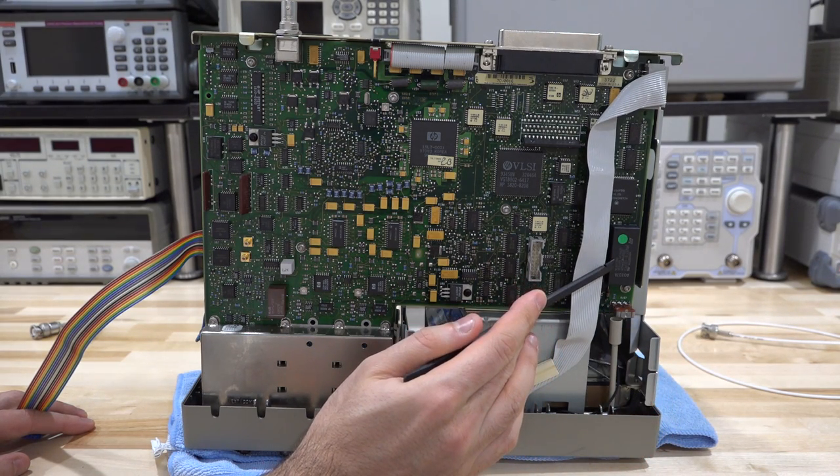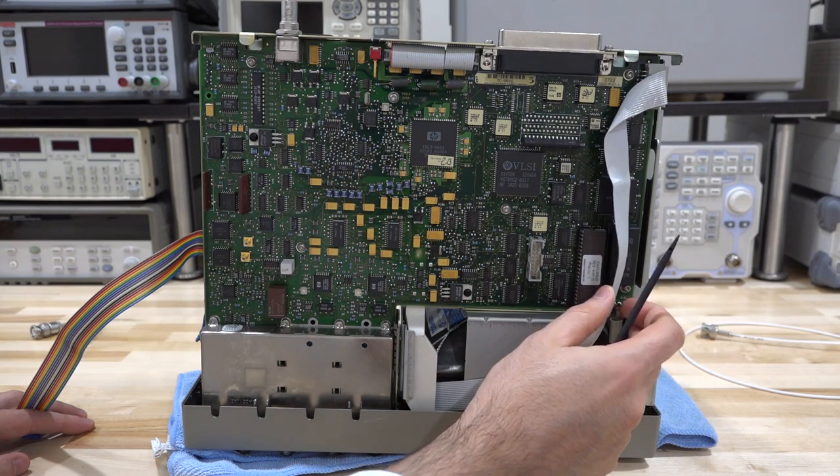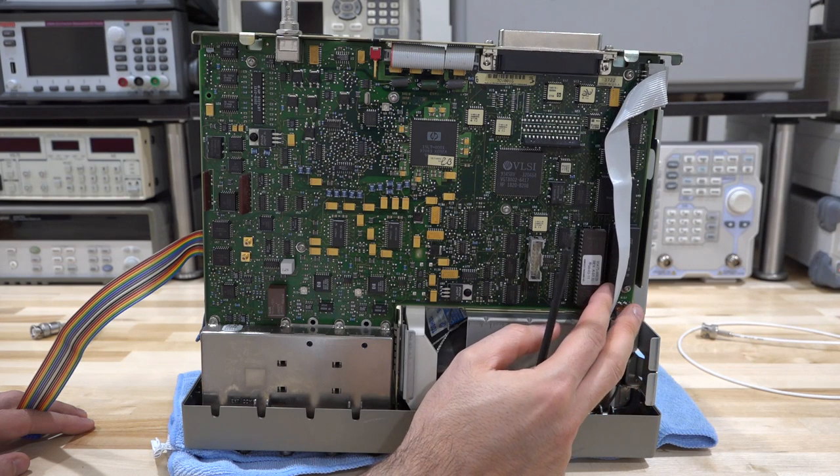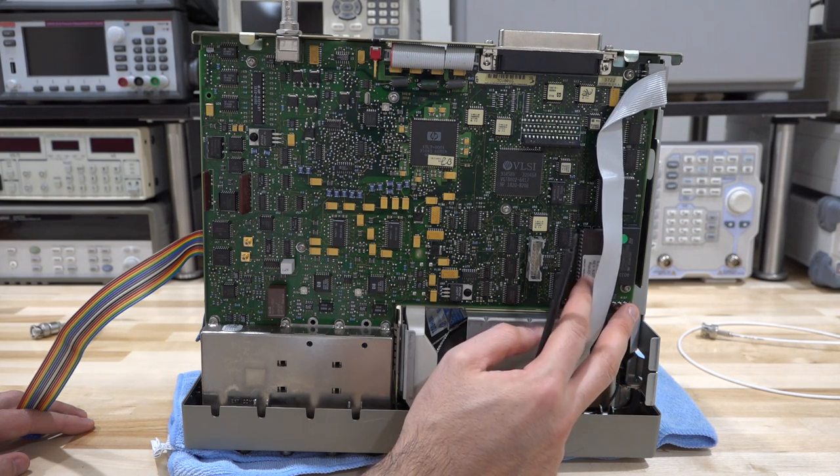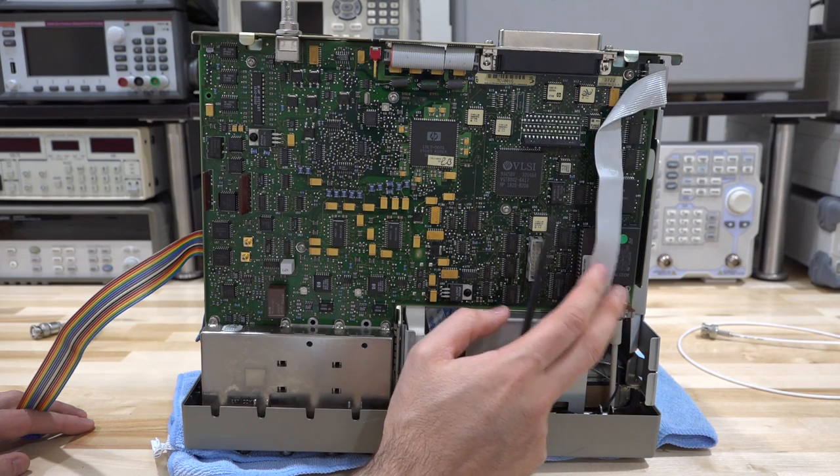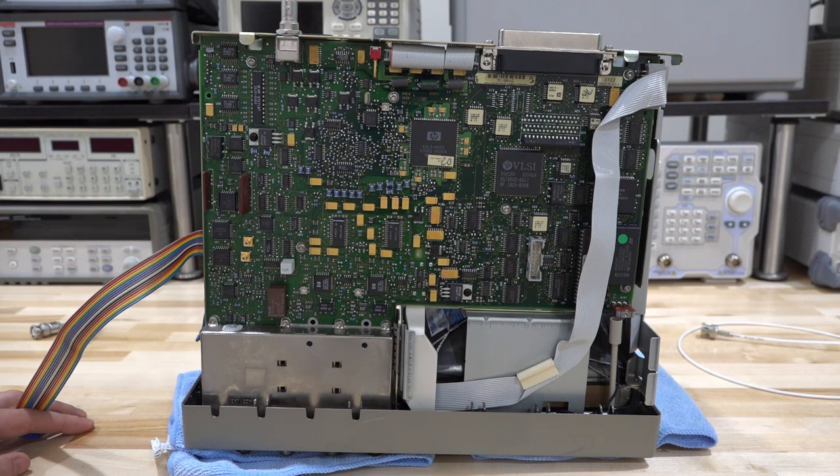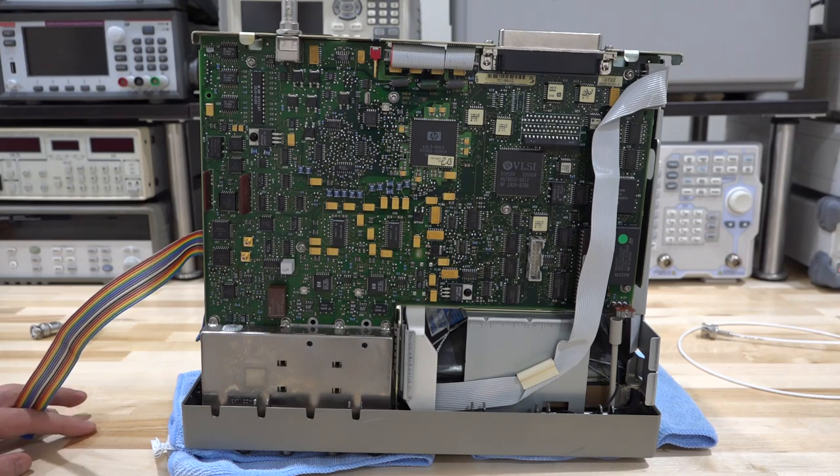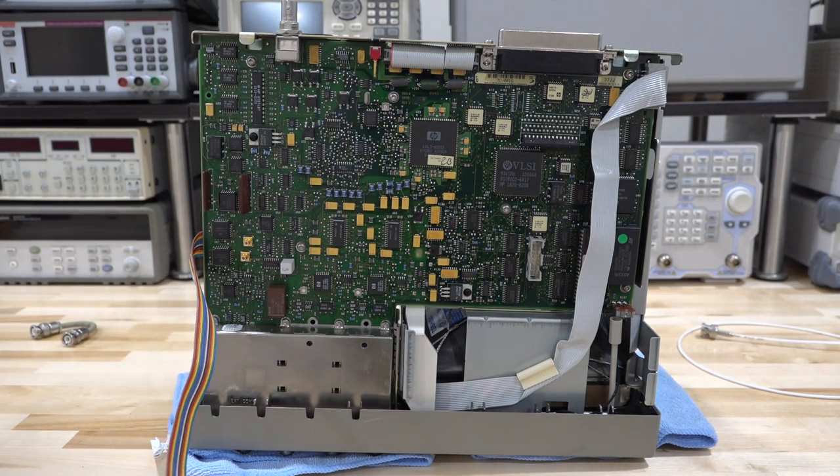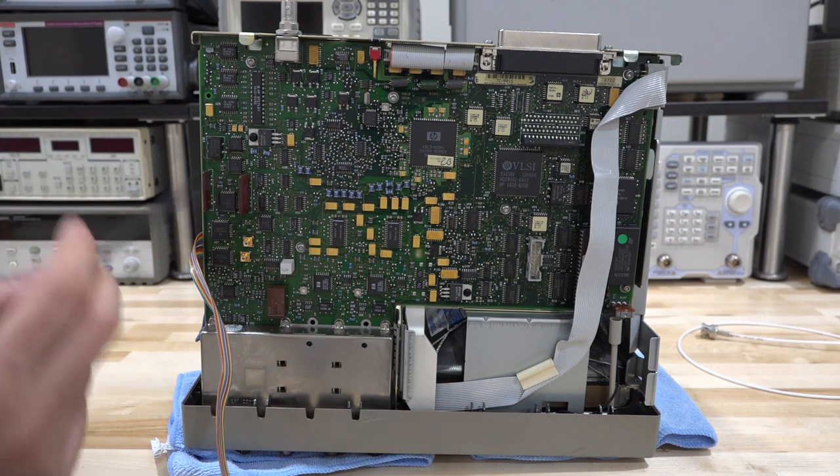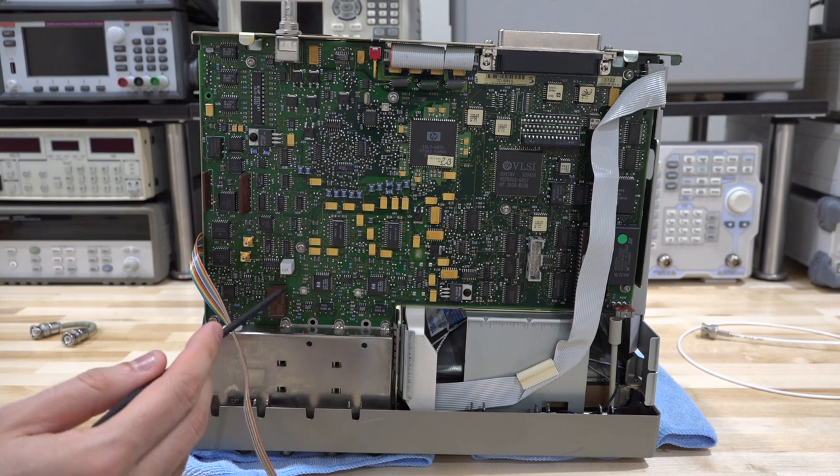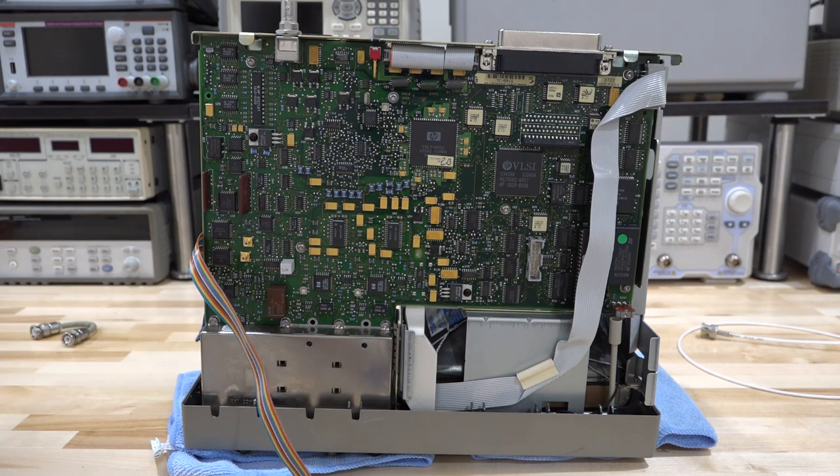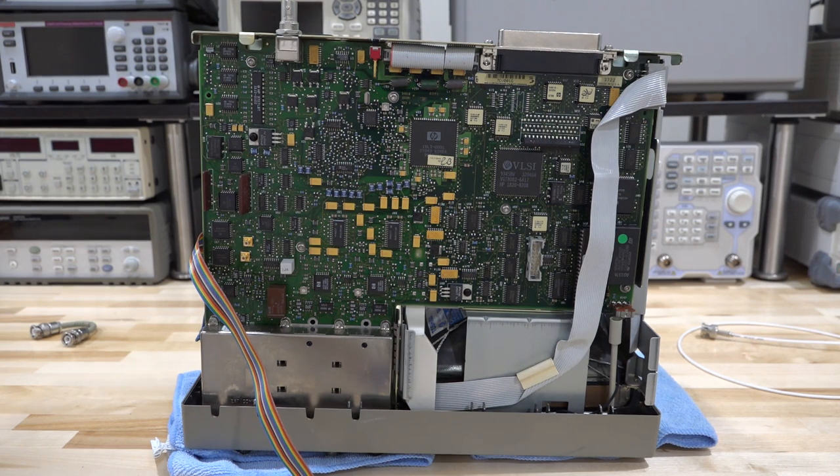So everything else looks pretty straightforward. There is our battery backup RAM, which will have all the calibration coefficients in there. And there is some firmware. Revision A, 1.32, some firmware in there. This is a UV-erasable part, which is also quite common for that era. Other than that, I don't see anything unusual there. This is, I believe, the trigger or the reference. That is the DC calibration output. This is for calibrating the front end. So I wonder if that's working, then we can try out and figure out if it's still functional. Some relay here. Some connectors there, perhaps for some options that this doesn't have, or some testing during manufacturing and so on.